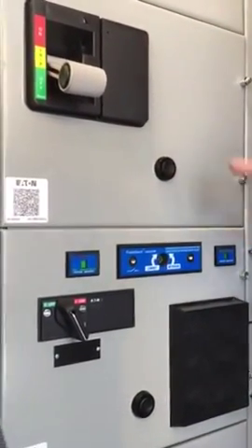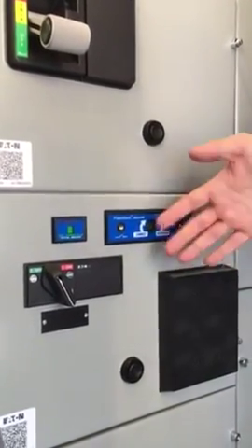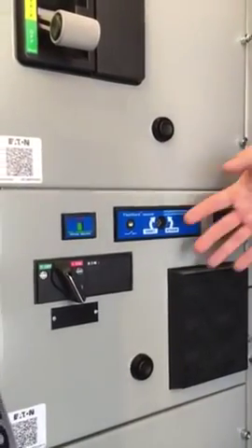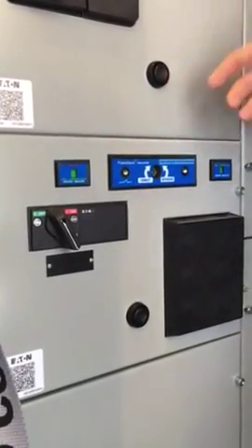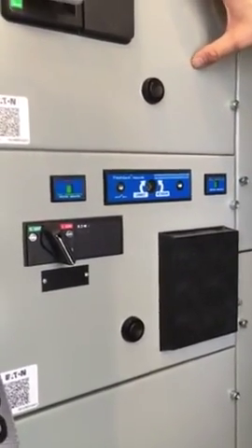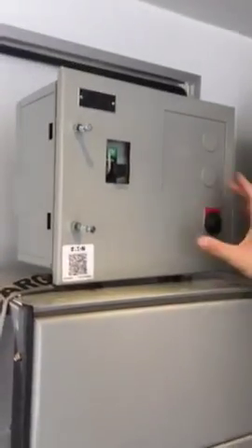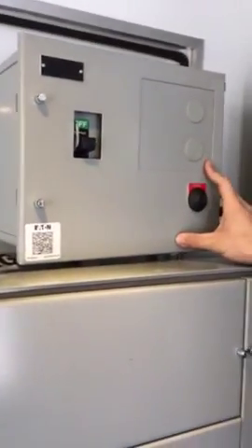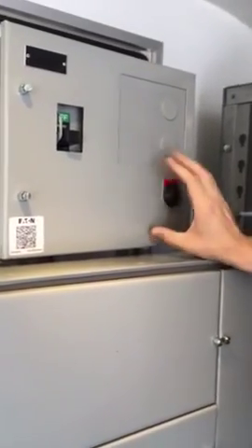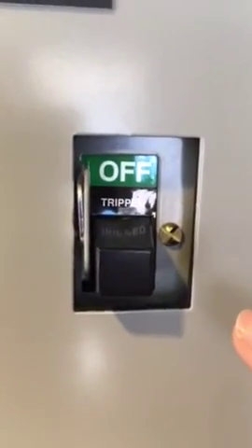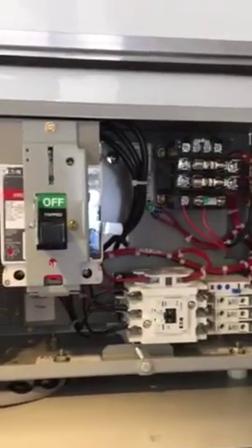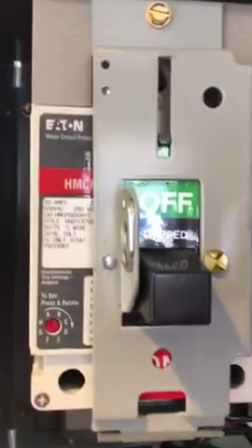Where this is simply for demonstration purposes to allow people to rack these MCC buckets in and out, and show the difference between them, and then show that we have the replacement capabilities for parts and pieces that go into these MCCs. At the top here, we show an MCC bucket that is a bolt-in replacement for another manufacturer. You see the difference in the type of operating handle that's not typical to Cutler Hammer or Eaton or Westinghouse, but the internals are 100% Eaton. So these are buckets that you can order that will go into another manufacturer's MCC, but all of the internals are Eaton.